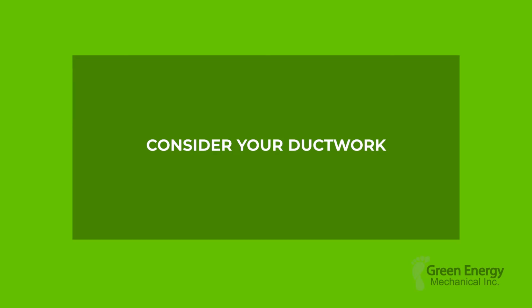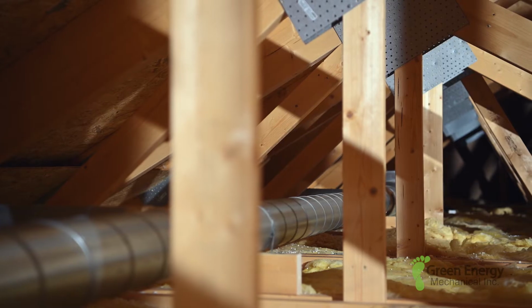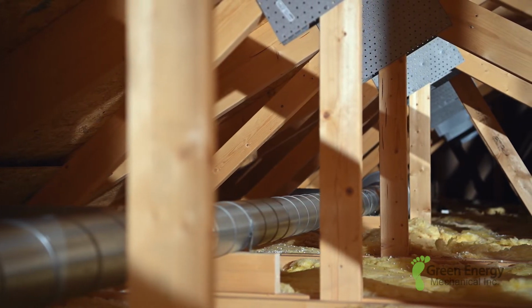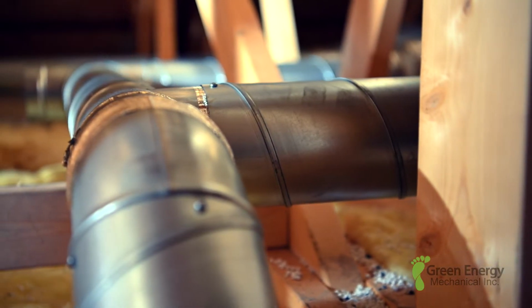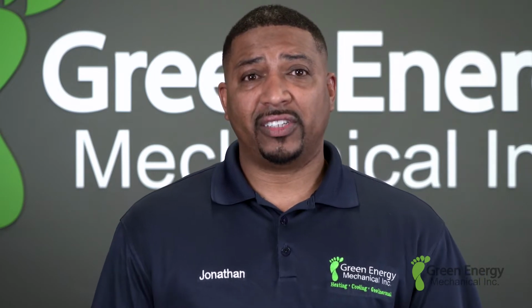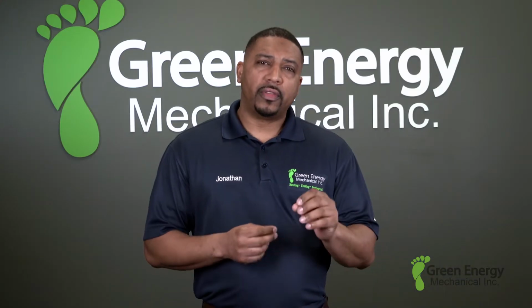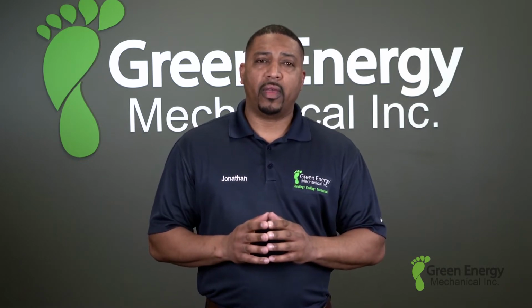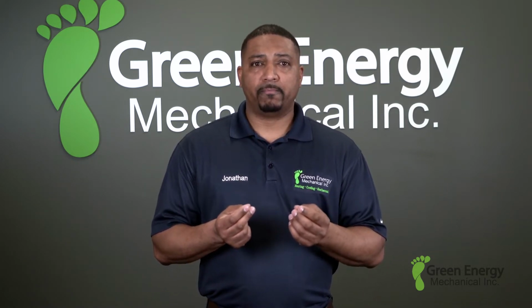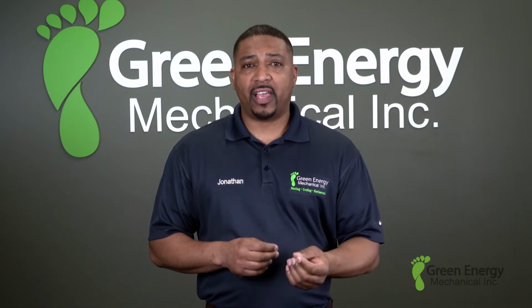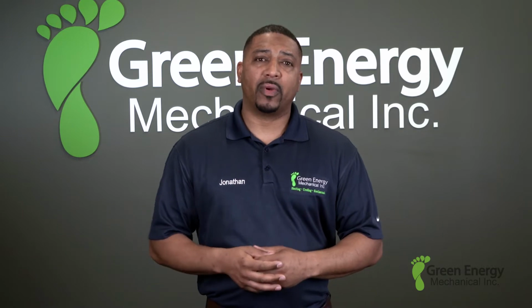Consider your ductwork. Many clients are upgrading an old oil or gas furnace with a new energy-efficient heat pump. When doing so, the contractor should be making sure the existing ductwork is sized correctly so it provides enough air to your indoor blower system. If not, it will be very loud when it runs, you will use more electricity, have lower energy savings, and eventually you'll need a new system entirely. To ensure that your current ductwork is sized right for your new heat pump, ask your contractor to show you on their duct calculator. In addition, they should provide a manual J and a manual D report to verify the ductwork is adequate. This is the time to address issues to make your system run better and provide better comfort.